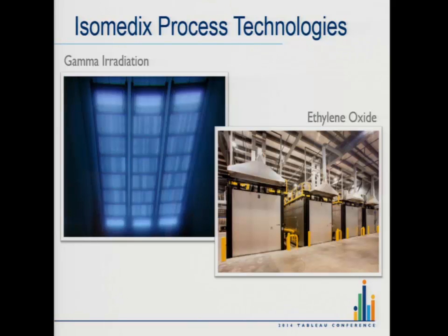The chamber itself is 6-foot concrete walls that have a maze type structure, so that the radiation bounces enough times that it won't exit the bunker, they call it. And there's never any transfer of radiation from the cobalt-60 to the product during that process.